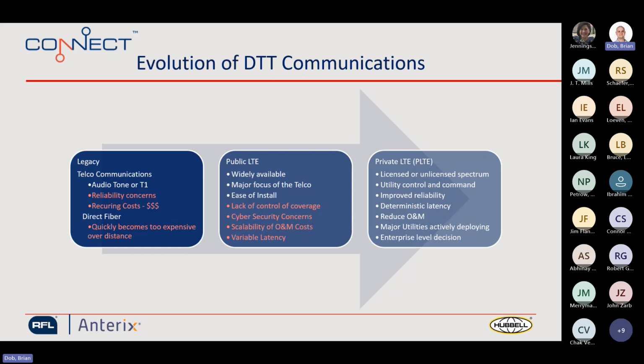The communications technology for direct transfer trip systems has evolved and is still evolving. You may be familiar with legacy type communications that were very common. These would have been audio tone circuits or phone lines leased from telco companies, could also have been T1 lines. A lot of those are not available anymore. In fact, the telcos at this point in many places are starting to sunset those and basically turn them off.